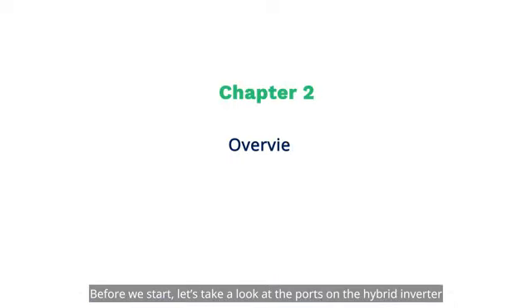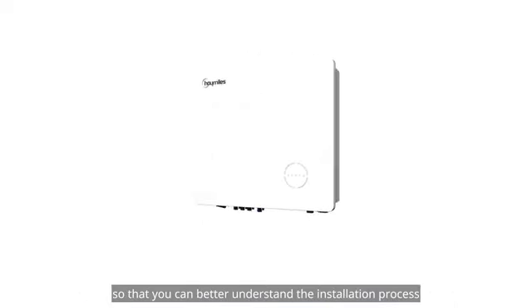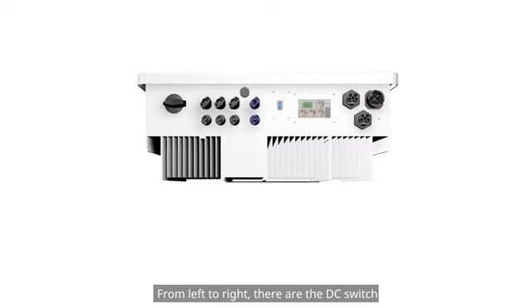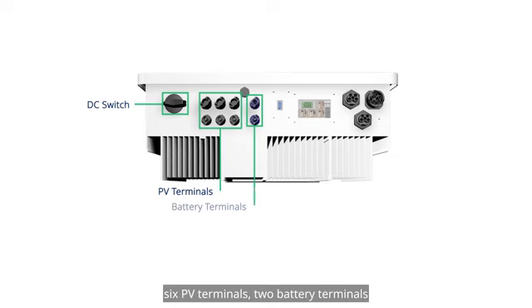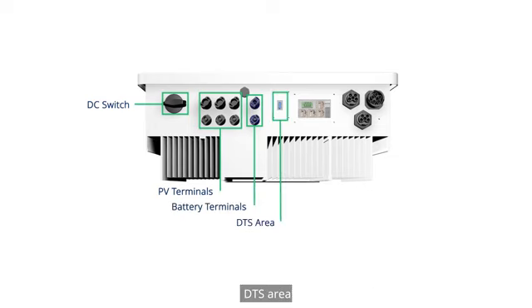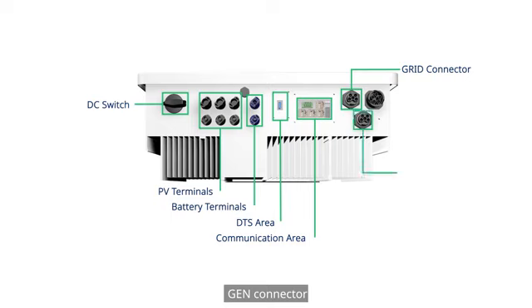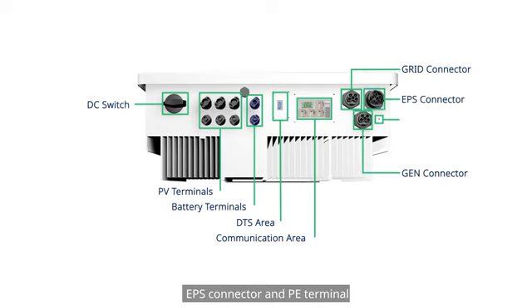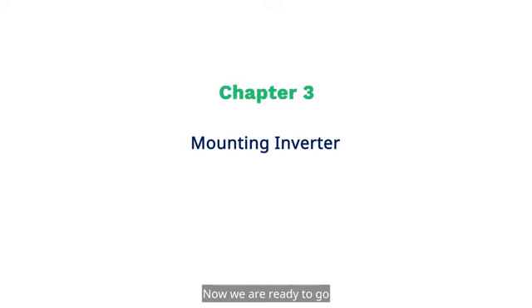Before we start, let's take a look at the ports on the hybrid inverter so that you can better understand the installation process. From left to right, there are the DC switch, 6 PV terminals, 2 battery terminals, DTS area, communication area, grid connector, generator connector, EPS connector, and PE terminal. Now, we are ready to go.